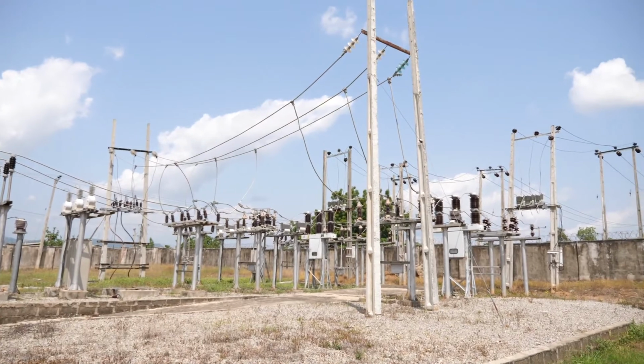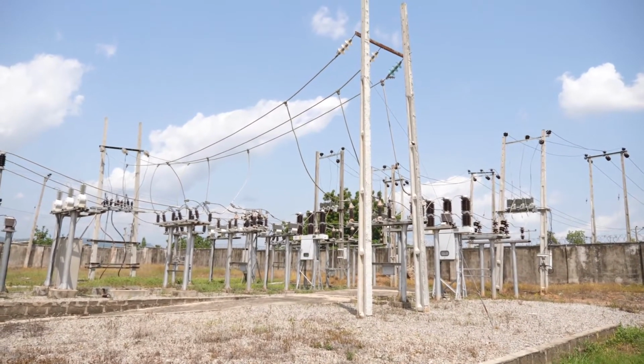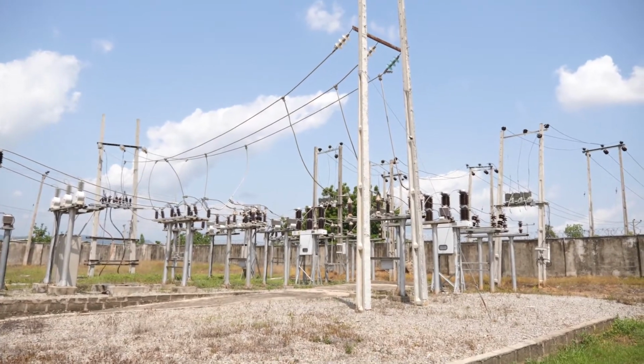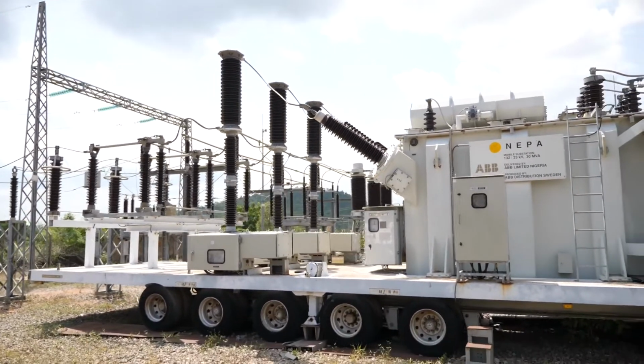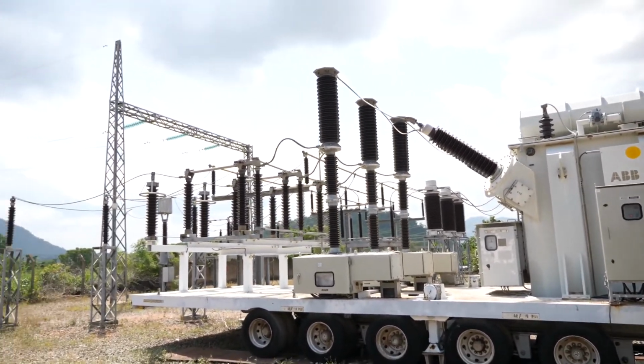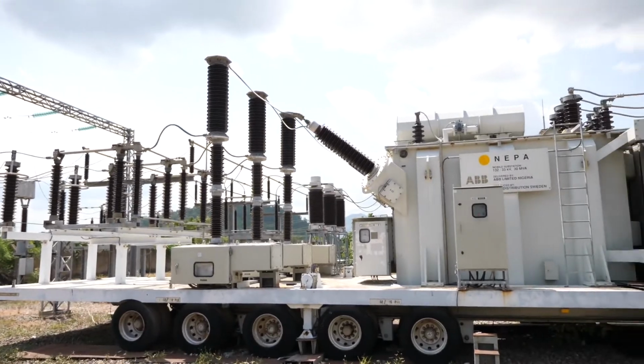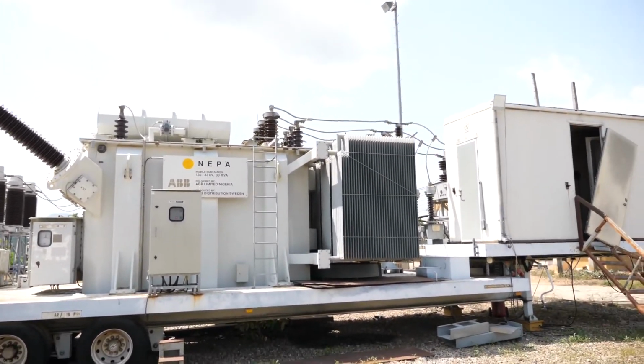The 132kV lines feed our substation, the 132 substation, and the ASCO steel plant, which has 2 double lines also. We also feed Okene and Opela from here on the 132 line. Our transformer is 162 MVA, with a maximum load of 129 megawatts, and we use it to feed the steel plants, Okene, and Opela.